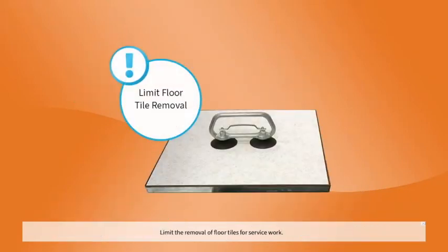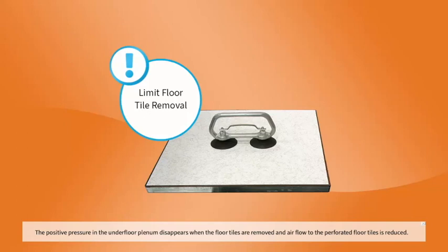Limit the removal of floor tiles for service work. The positive pressure in the underfloor plenum disappears when the floor tiles are removed, and airflow to the perforated floor tiles is reduced.